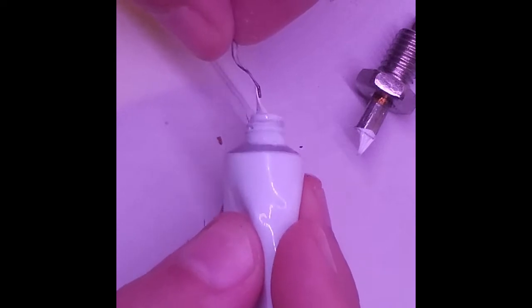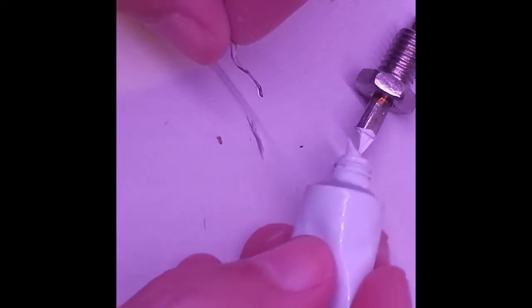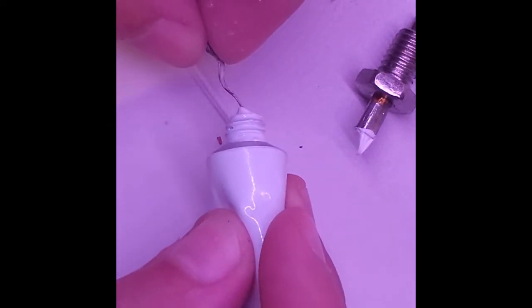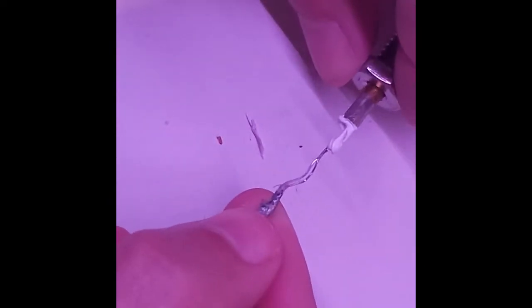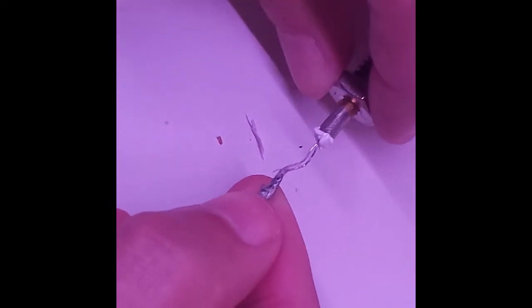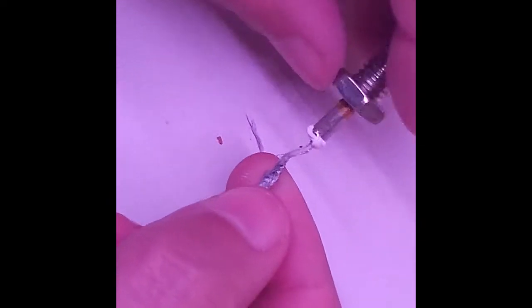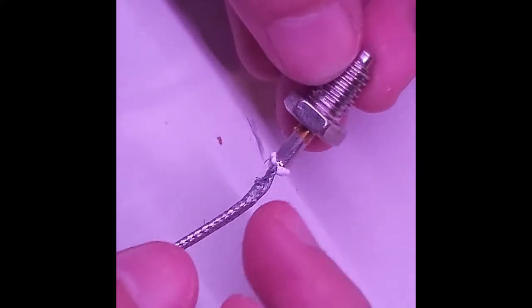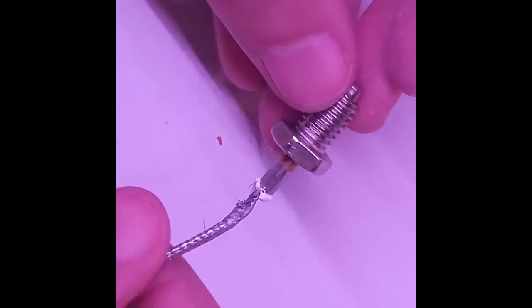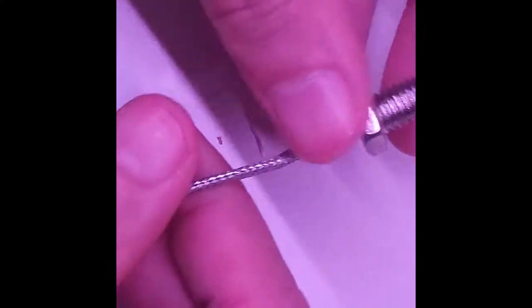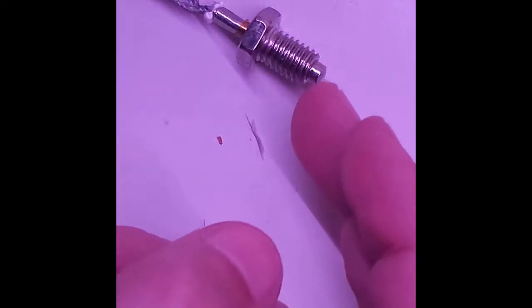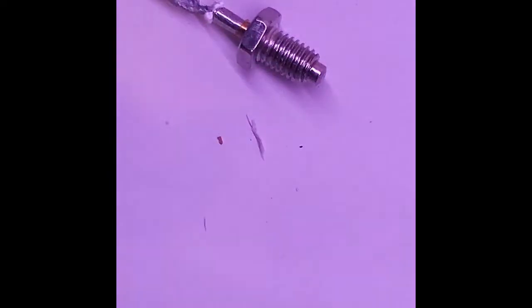You need to use like a toothpick and shove it down there, and then put some on the thermocouple itself. Then you can just push this down and really make sure you've filled up all of the hollow space in here so you get good heat transfer from the outer casing to the thermocouple inside.